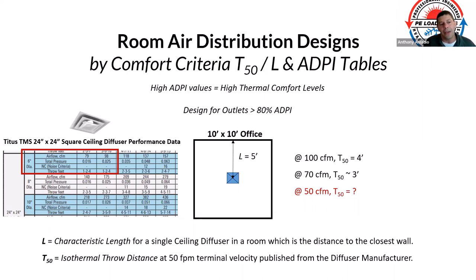You could look at the manufacturer specs and see, okay, at 100 CFM, at 80 CFM, what is my throw? What's my throw if it's smaller CFM? Sometimes you're stuck with clients who want to fill that grid with a ceiling diffuser. So we'll get right into that.